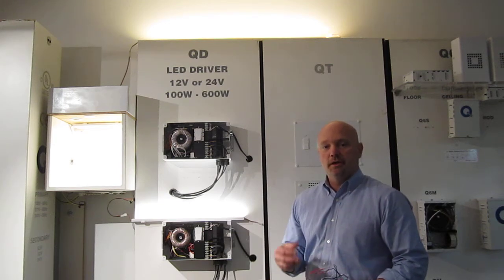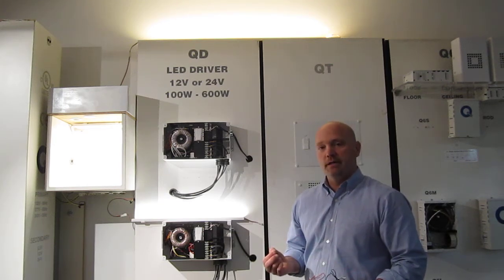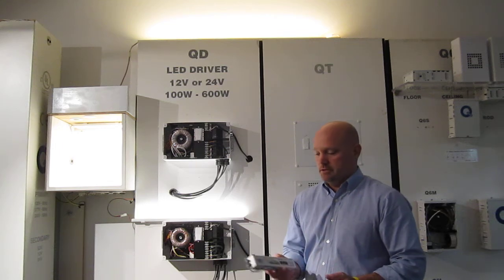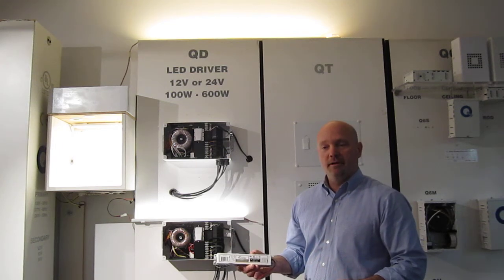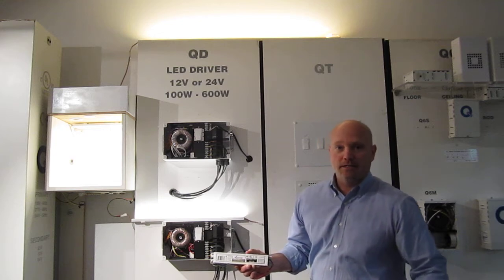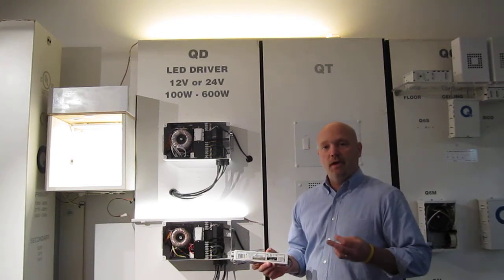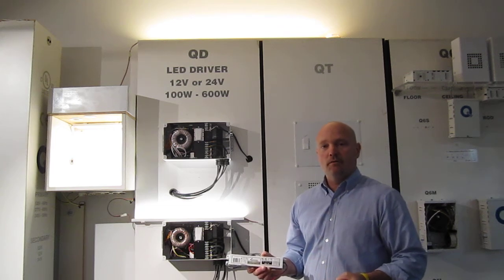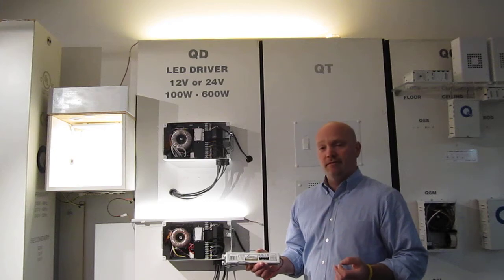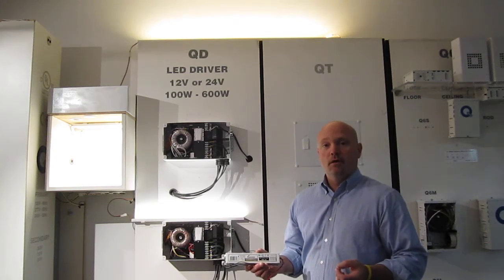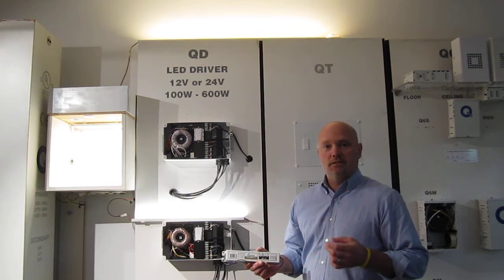The other challenge is when you have a job that has a large amount of LEDs on it, the contractor gets these relatively small drivers. They're limited to what is known as Class 2 output. That Class 2 limitation is 5 amps at 12 volts, which is 60 watts, or 4 amps at 24 volts, which is roughly 96 watts or 100 watts. Class 2 is a wiring method design that is safe from the risk of shock and safe from the risk of fire.